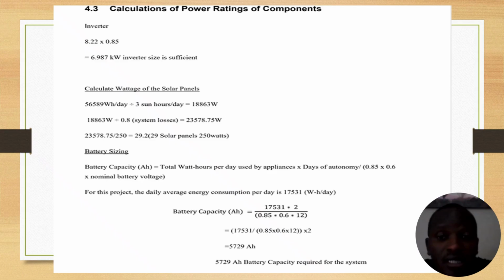So this is the sufficient size which is needed for the hospital, because on the previous slides I was showing you the calculation for the whole hospital, the power which the hospital is taking from the ESCOM. So now for the backup power, which is PV systems solar, it will need at least 6.987 kilowatts inverter size. This will be sufficient for the whole hospital in case of load shedding. There is the calculation wattage of the solar panels.